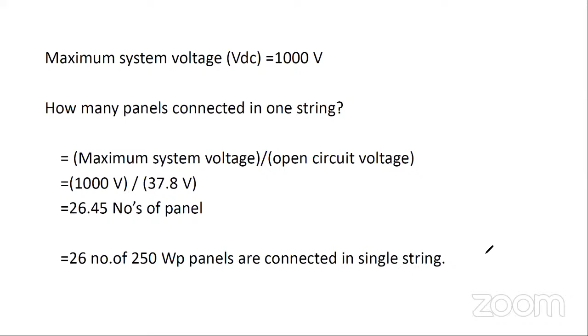The maximum voltage of the 5 kilowatt inverter is 600 volt. See, the maximum voltage of a PV module is 1000 volt, because a PV module can be used for a 5 kilowatt plant, a 10 kilowatt plant or even a 10 megawatt plant. It depends completely on which inverter it is connected to. So it is not only necessary to check the module datasheet for the number of panels in a string. It also depends on the inverter specification, which is why the maximum voltage of the inverter is needed here.